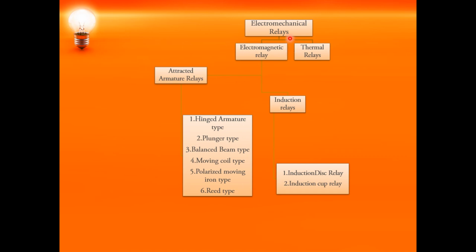Electromechanical relays operate by the mechanical forces which are generated on the moving parts either due to electromagnetic or electrothermic forces, which are created by the input quantity, that is either current or voltage. So if it is electromagnetic force, we categorize the relay as electromagnetic relay. If the force is generated by electrothermic, then we categorize it as thermal relays.